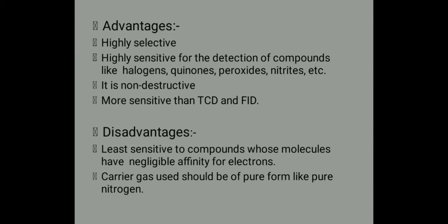Talking about the advantages, it is highly selective and highly sensitive for the detection of compounds like halogens, peroxides, nitrates, and quinones. It is non-destructive, and more sensitive than TCD and FID. Talking about the disadvantages, it is least sensitive to compounds whose molecules have negligible affinity for electrons. The carrier gas used should be of pure form, like nitrogen.